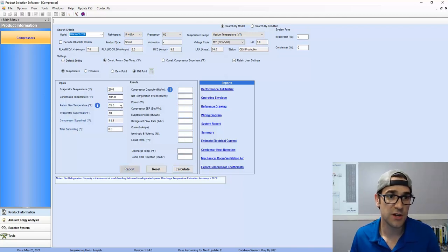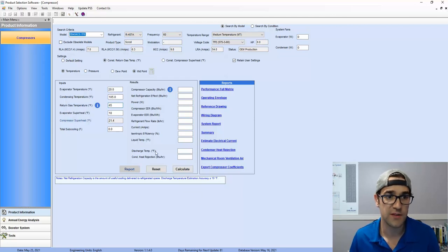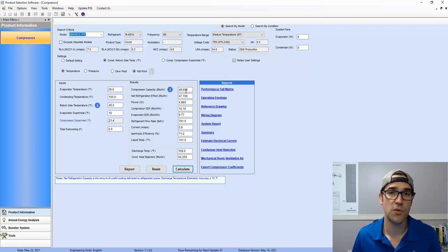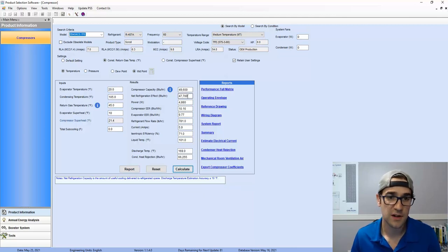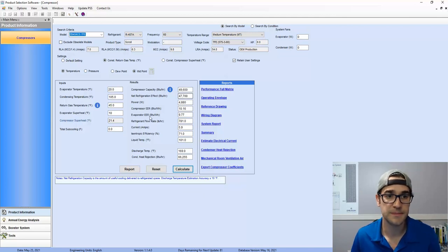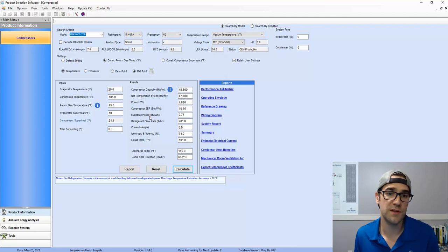Let's just say we change the return gas temperature. Let's say instead of 65, we've got 45 coming back. Calculate. So we get a little bit closer, but we're still 24% oversize here. We're 19% oversize again.